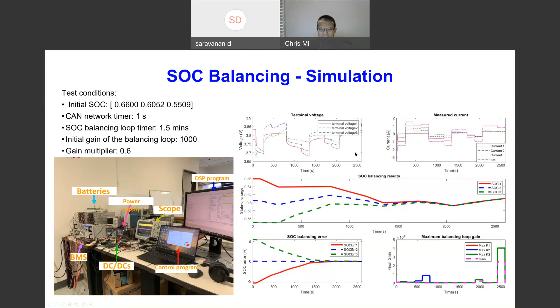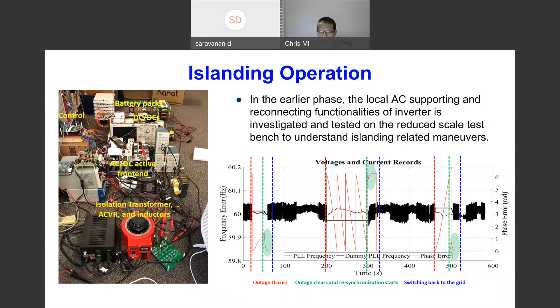I mentioned earlier the resiliency operation of the building using this energy storage system. During a power outage, we need to detect the outage and form an islanding operation. This islanding operation happens when the power outage occurs, and it takes anywhere from 17 milliseconds to a couple of seconds depending on conditions, so that we basically run an almost uninterrupted power supply for the building. We need to disconnect the system from the utility grid, and then start supplying power from the battery and solar to the building. That's how we operate the system.